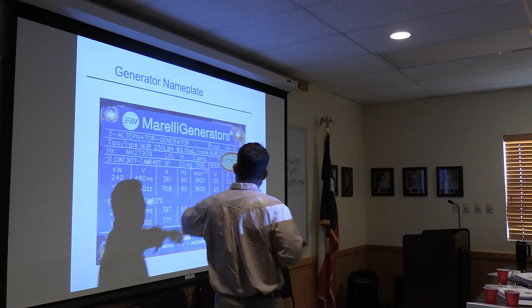Just like an electric motor, these gen sets are going to have their nameplate on it. There's a lot of good information on them, things you want to look for. Obviously, here's your kilowatts, the voltage, the amps, the hertz, and the RPMs. Other things you'd want to look at would be, make sure it's three-phase. And then your power factor, which in a lot is represented as cosine theta, but you're going to look for something that looks like a power factor.